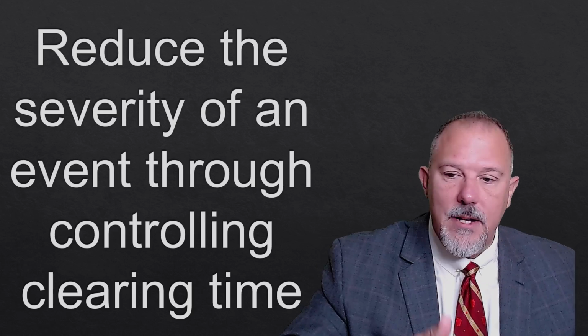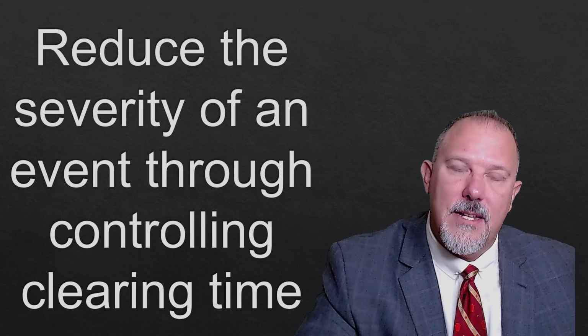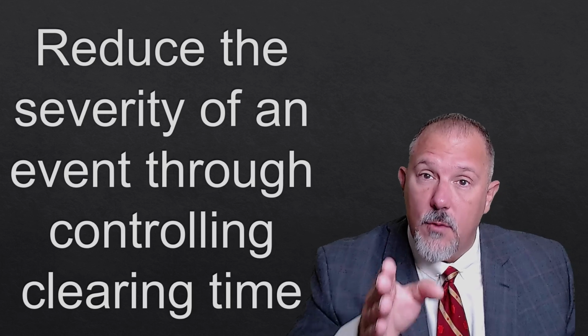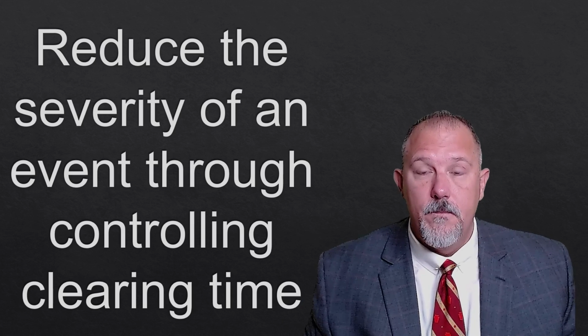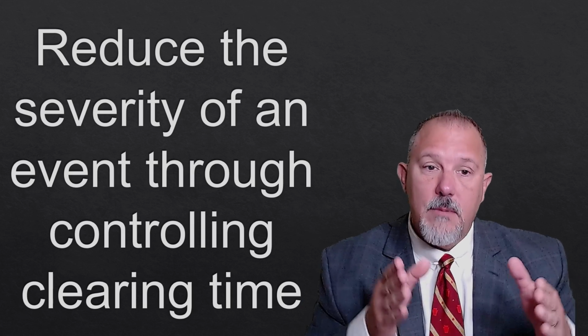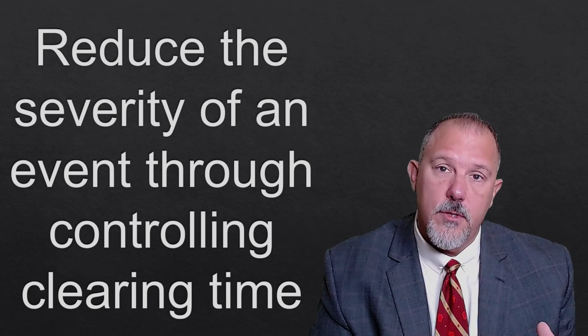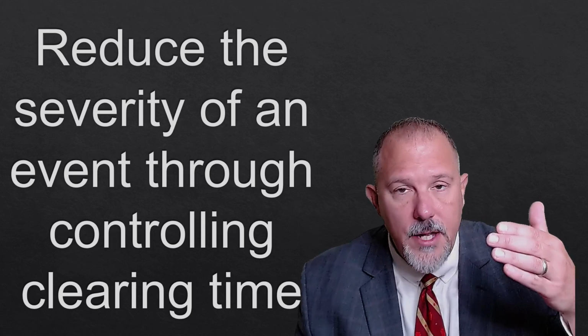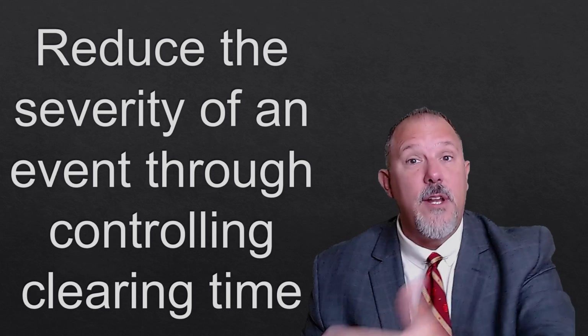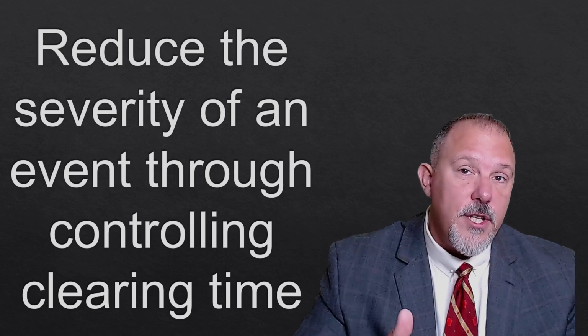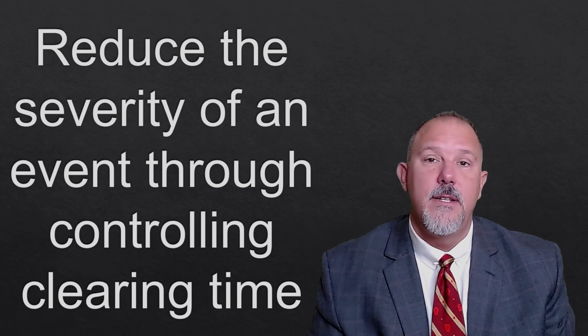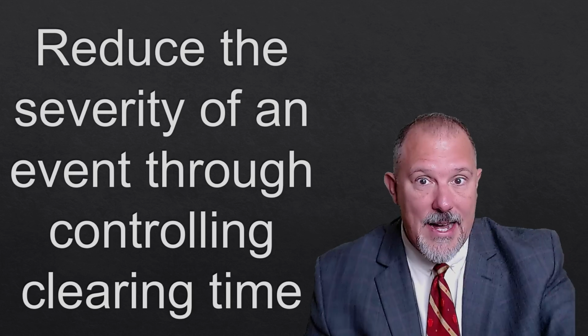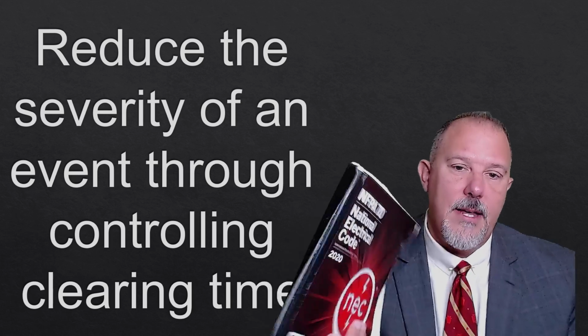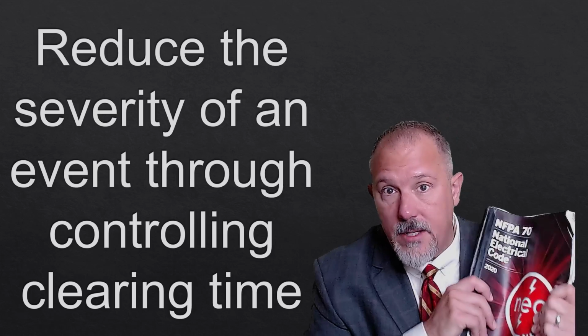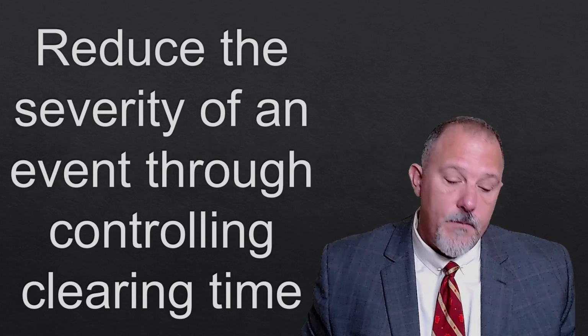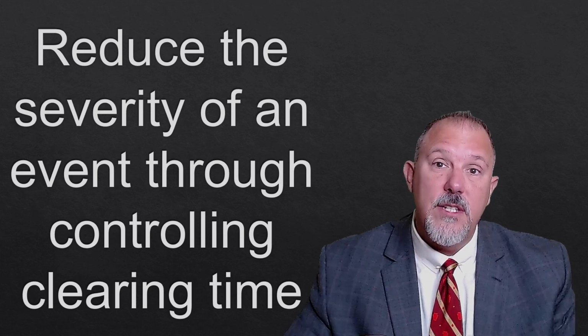Reduce the severity of the event through controlling clearing time. That is what 240.87 and 240.67 aim to do. If we can take these principles, either decreasing the likelihood of an event or reducing the severity of an event, when we design the system, let alone when we're applying this or even thinking about code requirements to put in as public inputs into the National Electrical Code to help increase safety.